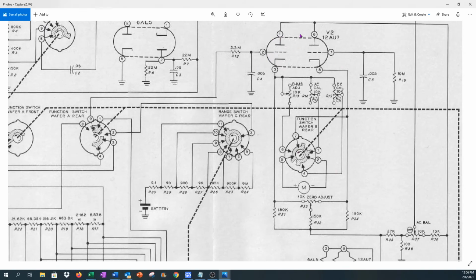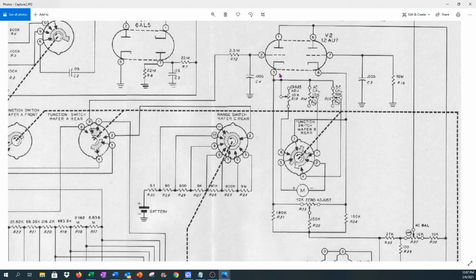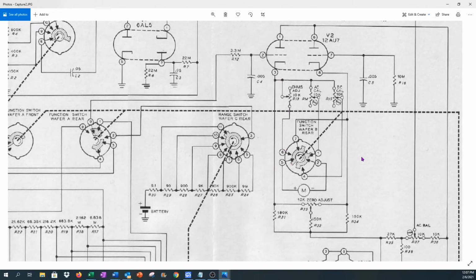This whole section right here works on the principle of a Wheatstone Bridge, basically. If you think about a Wheatstone Bridge, you've got your balancing resistors, and you can tell what an unknown resistor is by matching it with a variable resistor. This is kind of the same situation. Think of your old VOM meters, your volt ohm milliamp meters. That's how they work. They just stuck a galvanometer between a bridge, and you ran your voltage in there, and anytime the balance wasn't right, current flew through the meter and the meter movement. You can think of this the same way.